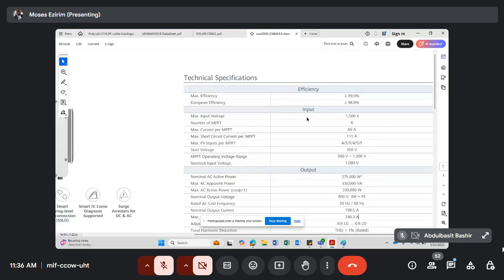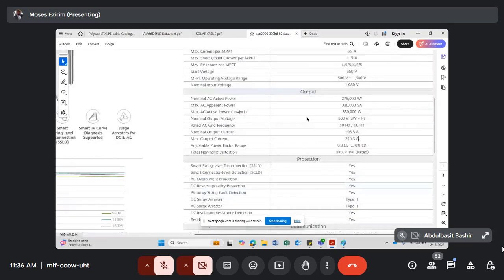Now an AC combiner box receives the output from different inverters. All right. So now I want to design it. I have five inverters, and the inverter that I'm using is this inverter. Now looking at this data, the maximum output current of the inverter is what? 240.3. So now which breaker am I going to use? 240.3 is not in the market. So which one am I going to use? I will simply use 250 amps.